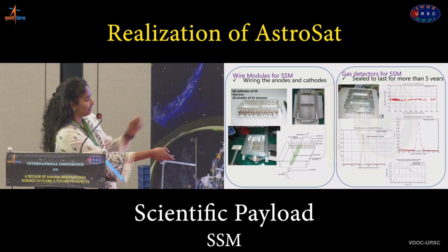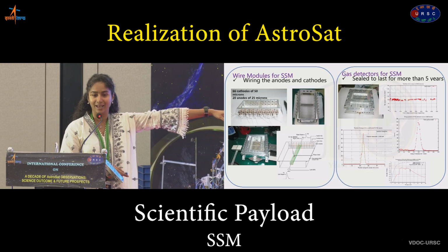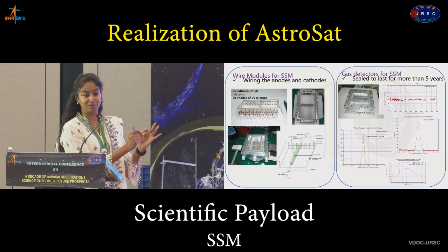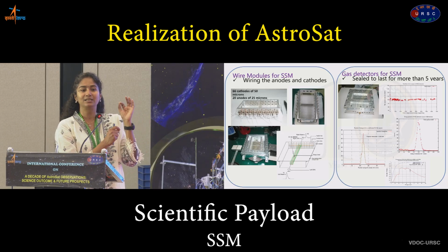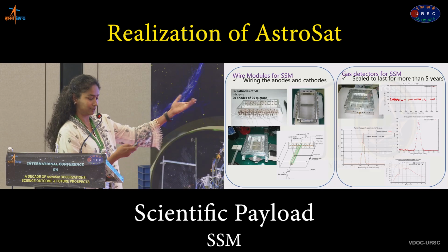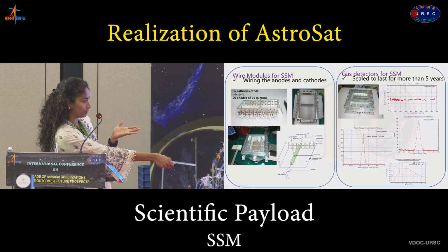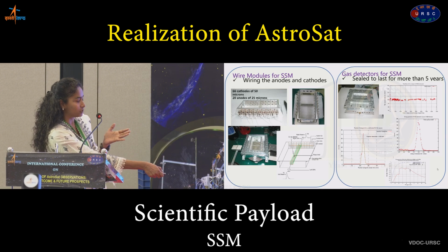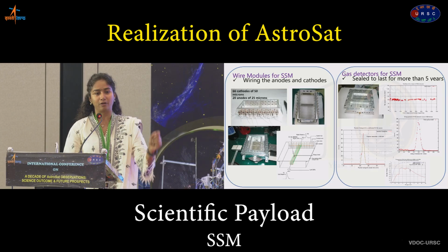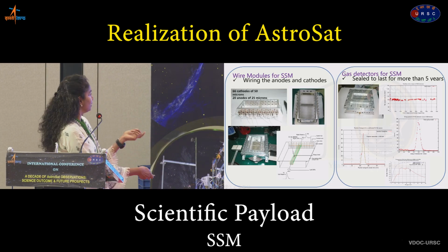This is a figure here, the one on the right top. For 3 years, the stability of a detector was tested, and it's not one detector. We had to do 3 detectors like this, establish the stability of the gain, and diligent calibration of the instrument. So the one here shows the energy resolution, and this is the position resolution, and this is the efficiency. So each of this anode wire, a cell in the detector, has to be tested for efficiency, position sensing, energy resolution, and taking it forward to imaging, the next one.